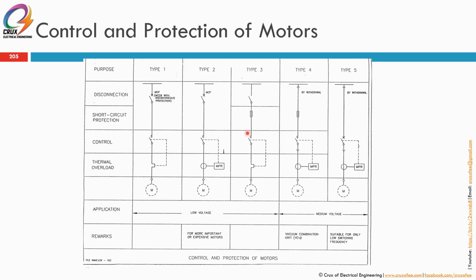Type number 3 is where we use an isolator plus fuse combination with a conventional overload relay. Type 4 is the same as type 3 but using a more modern CT with motor protection relay. While for type 5, this is using a circuit breaker. For example, in high voltage, this uses a vacuum circuit breaker together with the motor protection relay. Type 4 is for medium voltage, where normally we call this combination of contactor plus fuse a vacuum contactor unit.